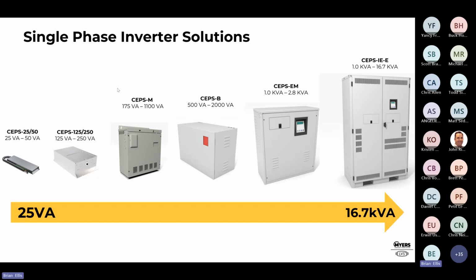Then we have the CEPS-M series, the 175 to 1100. This series gives you a few more bells and whistles. If you want BACnet integration, different things like that, there's a lot of different bells and whistles that are available on the CEPS-M. The CEPS-B series is only available in 4 sizes. It's 500, 1,000, 1,500, and 2,000. It's really meant to be bare bones. You can do automatic testing. If you add that, you can have a few output breakers. But other than that, it's just your standard inverter, very low cost solution for your customers.